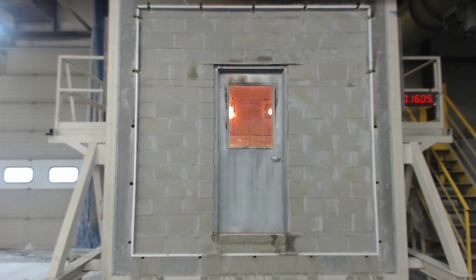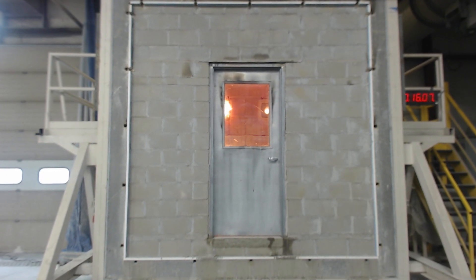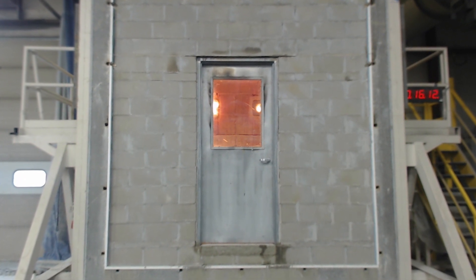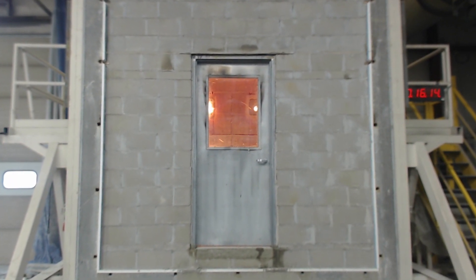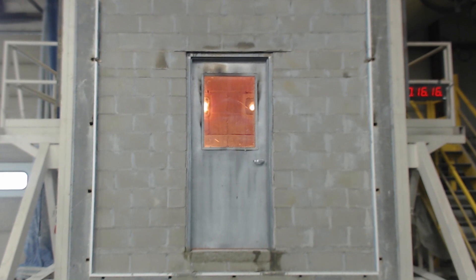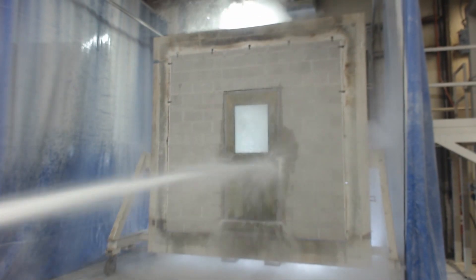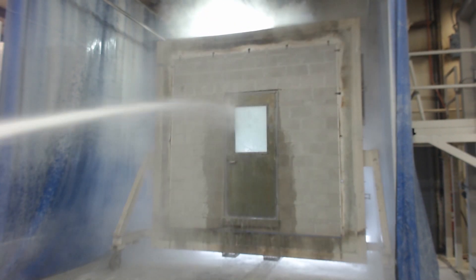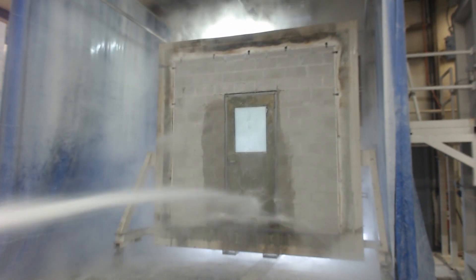These ratings are earned after passing a fire test with an accredited laboratory, such as UL or Intertek-Warnock Hersey. The fire door test uses a furnace to replicate the effects of a fire. After the fire test, a hose stream test is performed to verify the door can withstand the force from a fire hose and remain in the closed position.